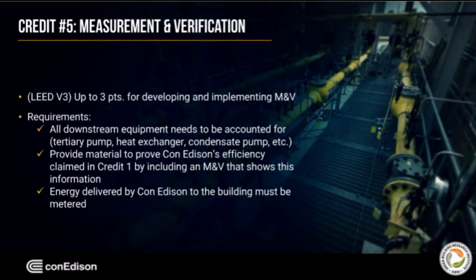The U.S. Green Building Council awards 3 points to projects that develop and implement a measurement and verification plan. The requirements are that all downstream equipment needs to be accounted for, like tertiary pumps, heat exchangers, condensate pumps, etc. Material needs to be provided to show the district energy system's efficiency claimed in Credit 1 by including a measurement and verification plan that shows this information, and the energy delivered by the DES to the building must be metered. Con Ed complies with all of these requirements.